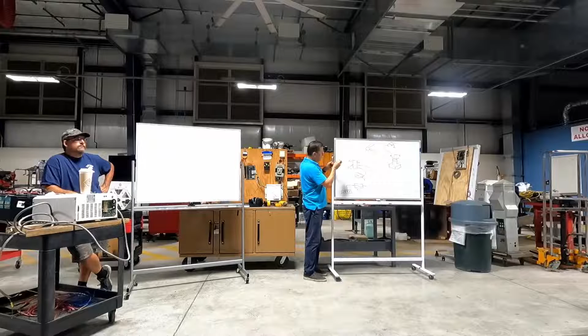Be careful with the installation of the bilge pump switch, the manual/automatic switch you install. The input power in the middle comes directly from the positive bus bar, not from a main breaker. You don't have a main breaker in the DC panel labeled bilge pumps. No, the bilge pump has power all the time.